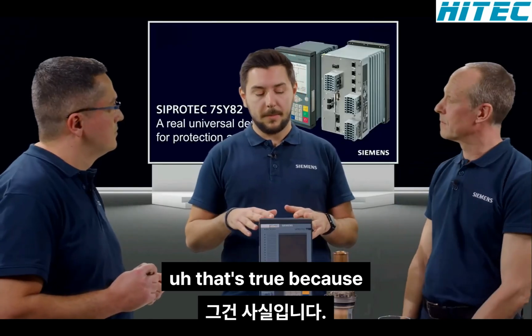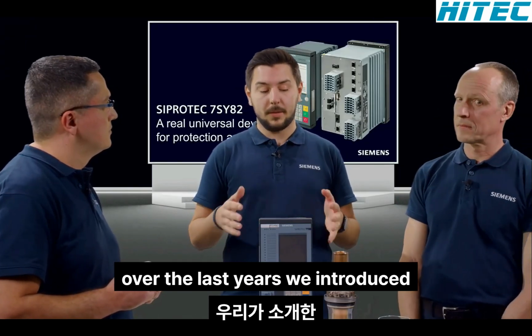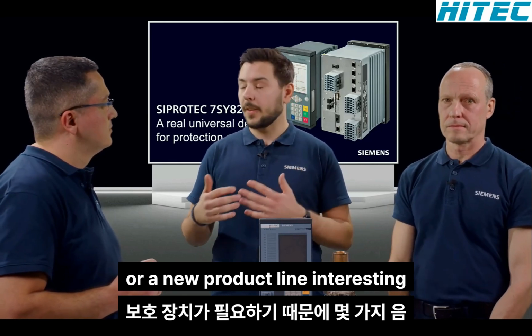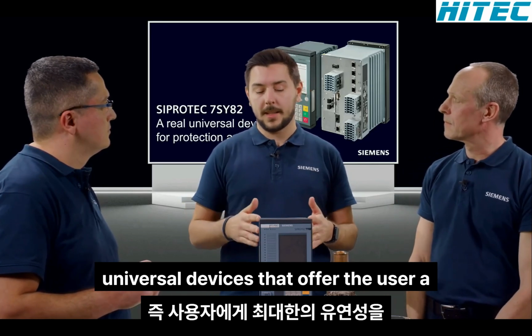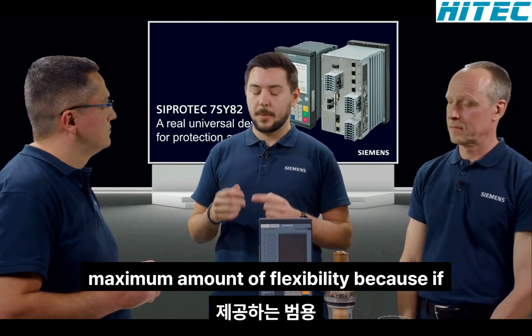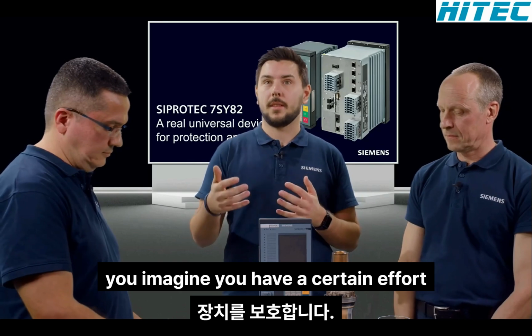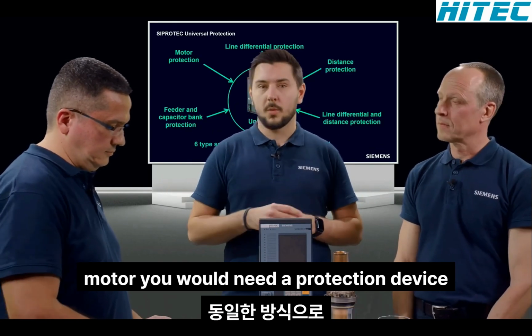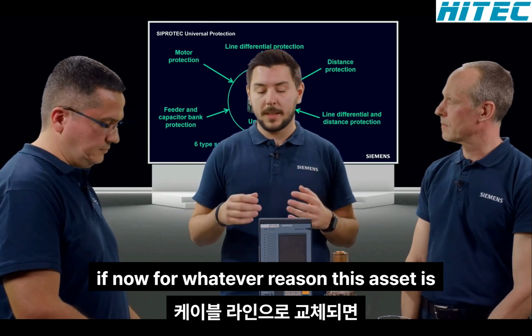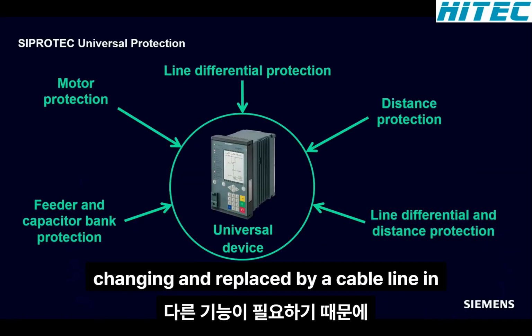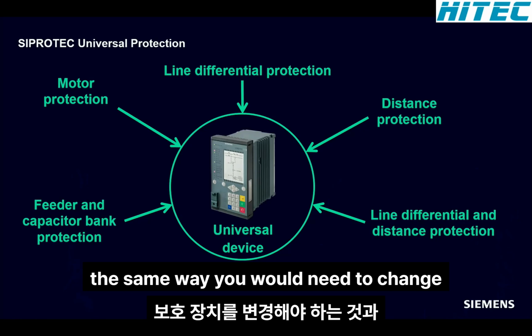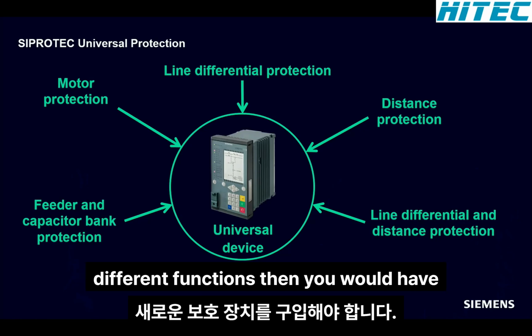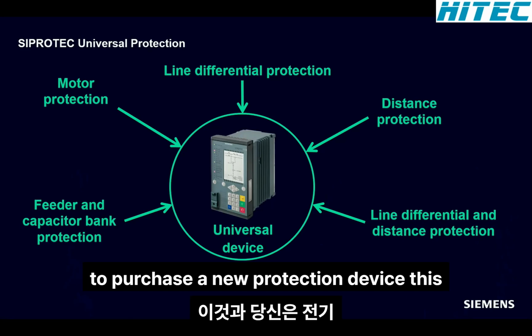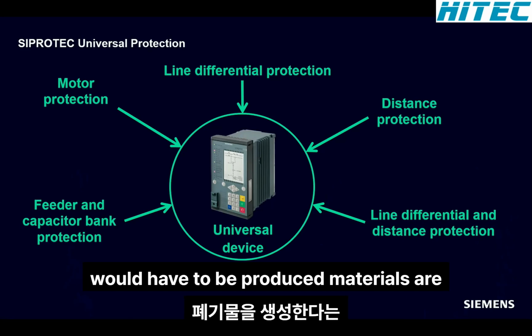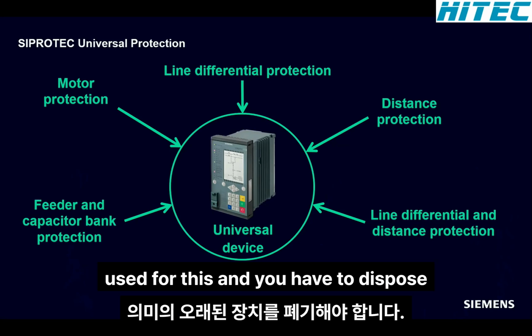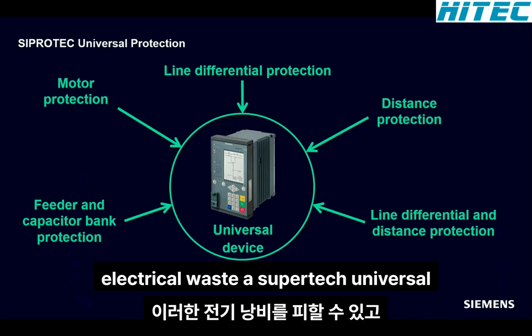That's true, because over the last years, we introduced a new product line into our SIPROTEC 5 platform, namely the universal devices that offer the user a maximum amount of flexibility. Because if you imagine you have a certain asset that you want to protect, for example, a motor, you would need a protection device. If now, for whatever reason, this asset is changing and replaced by a cable line in the same bay, you would need to change your protection device because you need different functions. Then you would have to purchase a new protection device. This would have to be produced. Materials are used for this. And you have to dispose of the old device, meaning you are creating electrical waste.